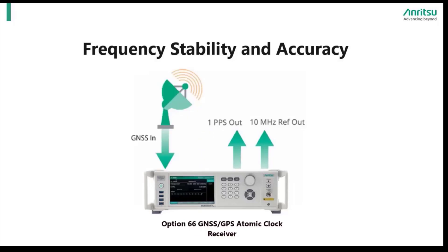Option 66, GNSS (Global Navigation Satellite System) and GPS (Global Positioning System) Atomic Clock Receiver, also provides atomic clock accuracy. These references rely on satellites for a synced and accurate timebase reference. One of the nice qualities about this option is that it can further enable the in-field calibration option.